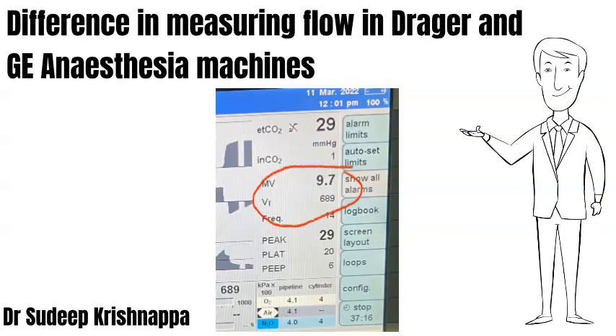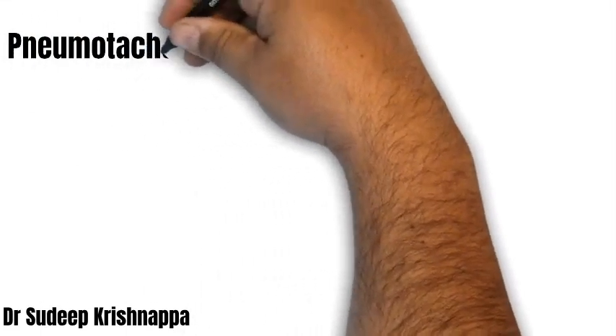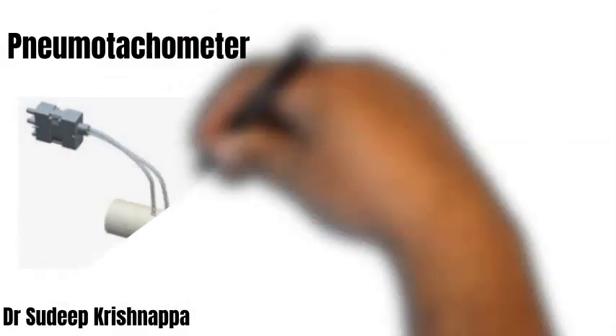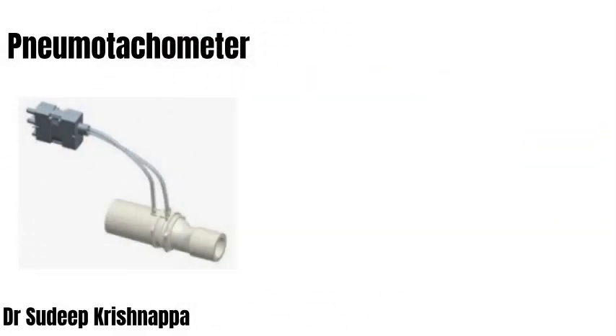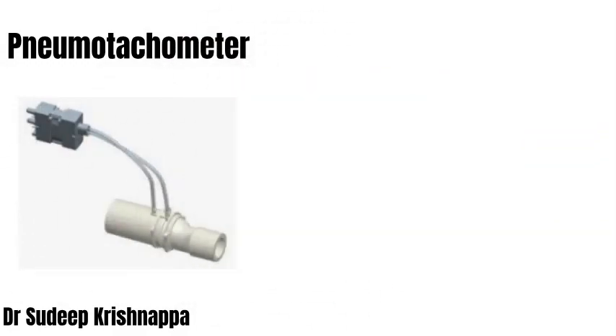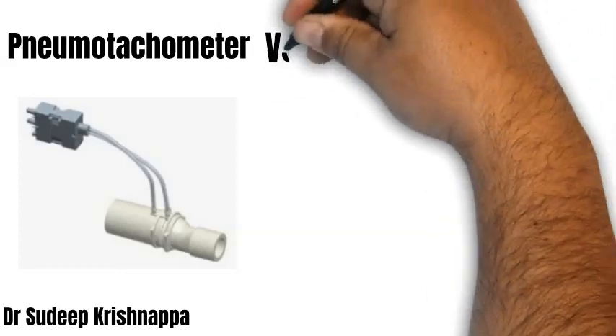GE and Drager machines are among the most commonly used anesthesia workstations. While the GE machines use a device called a pneumotachometer, Drager machines use another measuring mechanism called a hot wire anemometer.